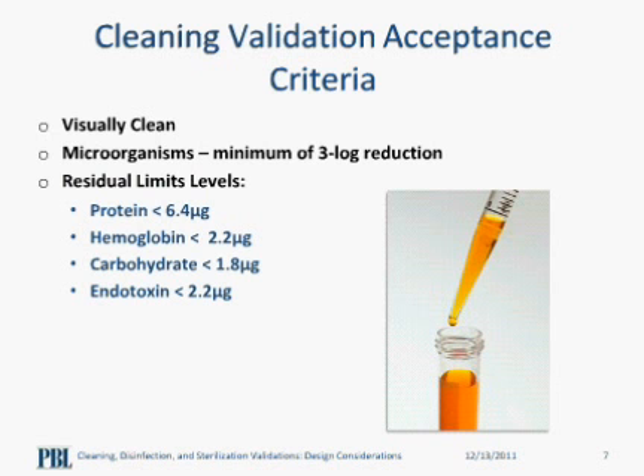First, we inspect that the device is visually clean after the cleaning procedure. For those of you with long lumens or channels in your device, this visual inspection will include observing clear liquid coming out of those channels or lumens. Since we inoculated with a known concentration of soil, we can calculate the reduction in soil by comparing the positive controls with the cleaned devices. For microorganisms, a minimum of a 3 log reduction must be met. A screening for residuals must prove to be below certain limits. In micrograms per square centimeter, protein must be less than 6.4, hemoglobin less than 2.2, carbohydrate less than 1.8, and endotoxin less than 2.2. If your device meets these limits, the cleaning procedure is validated.